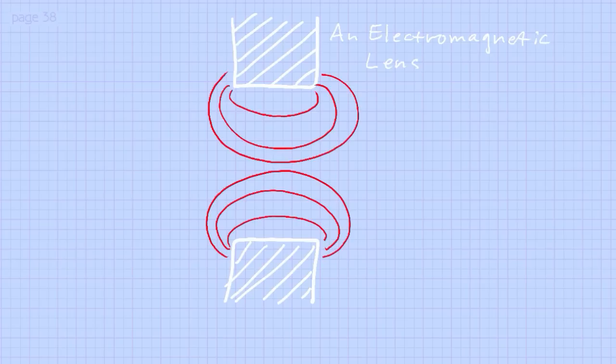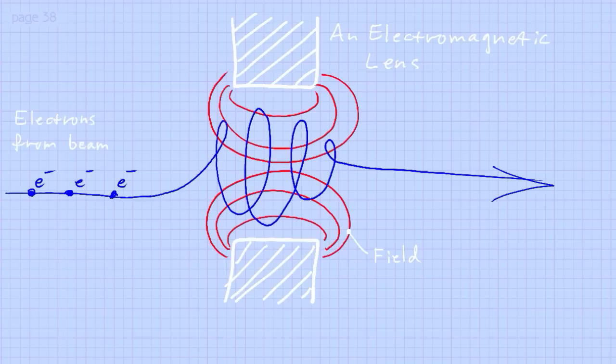Basically it works exactly like your eye, which can change the focusing effect by adjusting the curvature of the lens. One drawback with electromagnetic lenses is that when the electrons are focused by the lens, they make a spiral pathway as they go through the lens. That will cause the image produced on a screen below to behave differently.